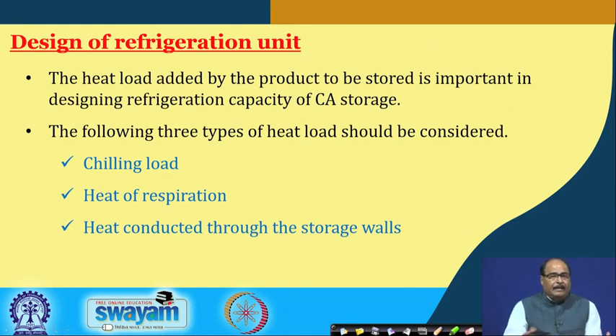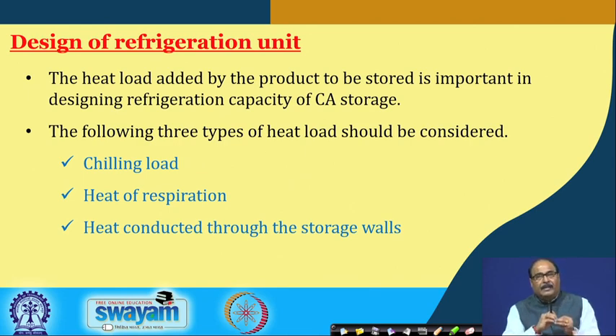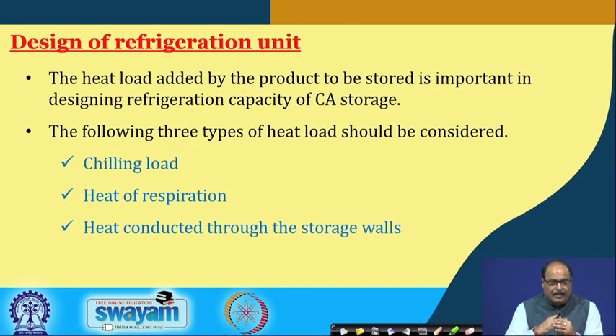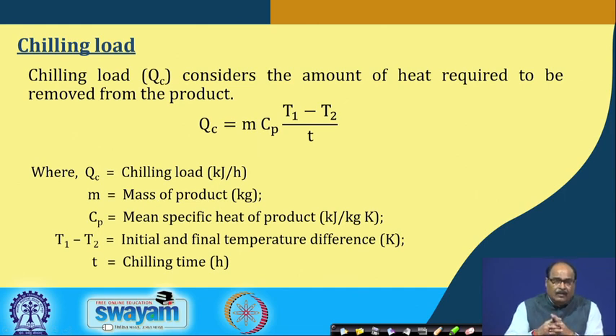Now let us discuss one by one the various aspects like heating system, CO2 generating system, O2 generating system — what are the various factors included in their design and load calculation. First, the design of a refrigeration unit: the heat load added by the product to the storage is an important consideration for calculating the refrigeration capacity of the control atmosphere storage system. There are three types of heat load which should be considered: number one, chilling load; then heat of respiration; and heat conducted through the storage wall.